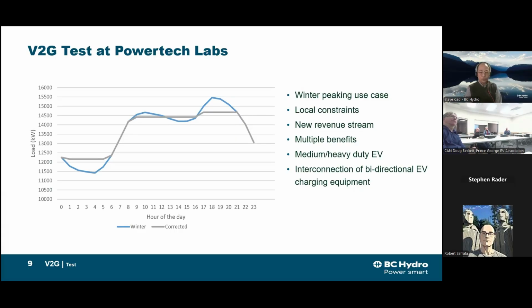When we tried to discharge at 60 kilowatts, that's the rated discharge capacity for the charger, it was pretty steady and the performance was pretty good. But when we dialed it down to 20 or 15 kilowatts to extend the duration of the discharge for the battery, it wasn't as steady. If we set it at 20, we weren't getting 20 - it was fluctuating anywhere from 10 to 25, 30, and so on. So there's still some work to be done there.